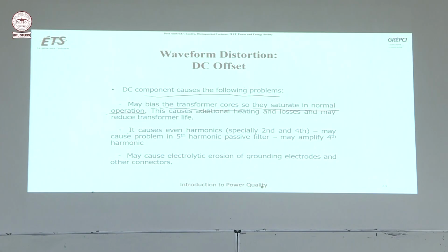DC component causes even harmonics, second and fourth. It may cause problems in a fifth harmonic passive filter. The fifth harmonic filter may amplify the fourth harmonic. It may also cause electrolytic erosion of grounding electrodes and other connectors.